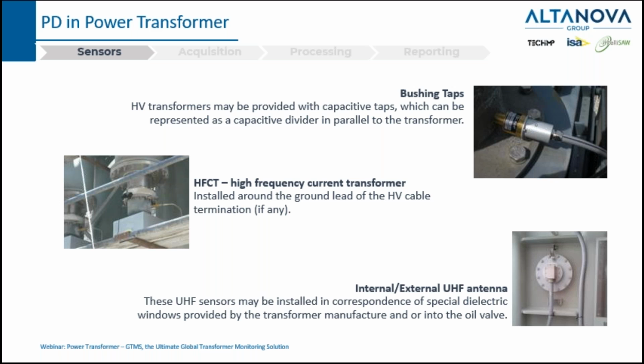And then we have to process all the information and make a report, or have all the information inside the monitoring system. Regarding the sensors, we have seen very quickly the bushing taps. High voltage transformers are normally provided with these capacitive taps, which basically represent a capacitive divider in parallel to the transformer. This is our favorite sensor when we have to detect partial discharge, not only in the bushing but also in the transformer.